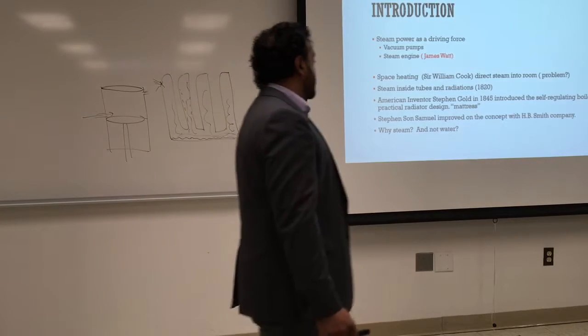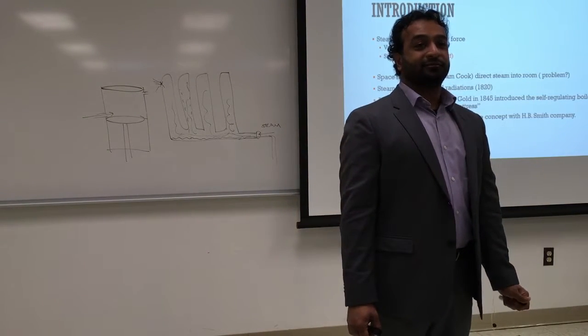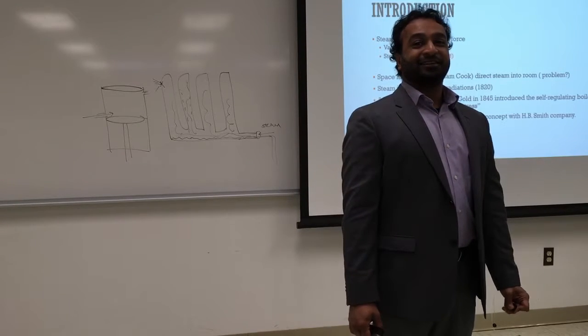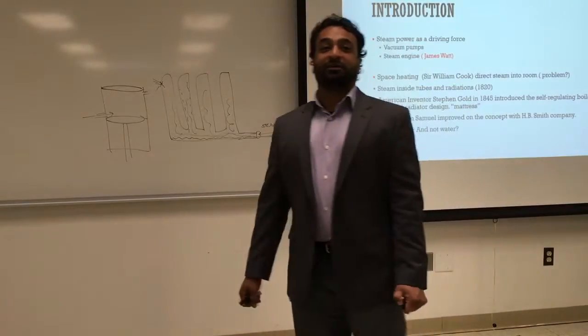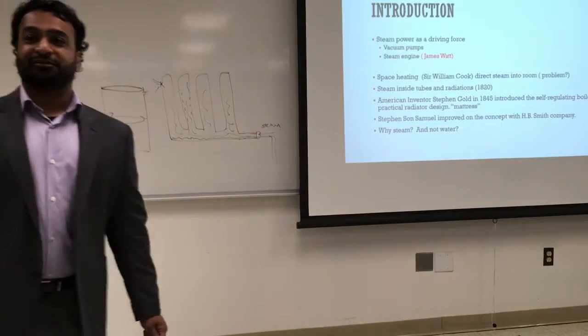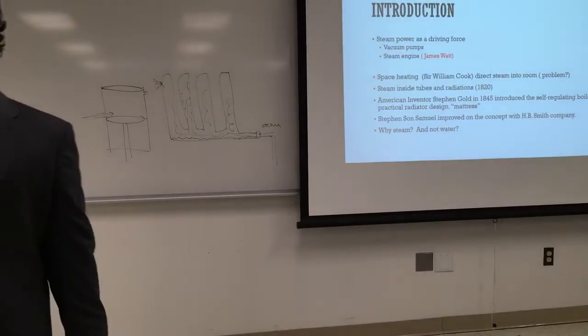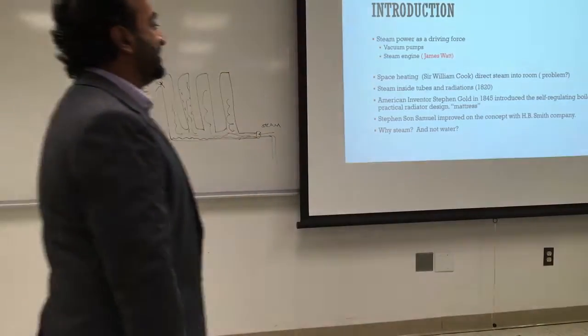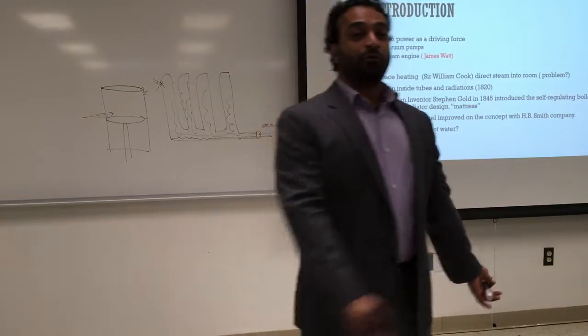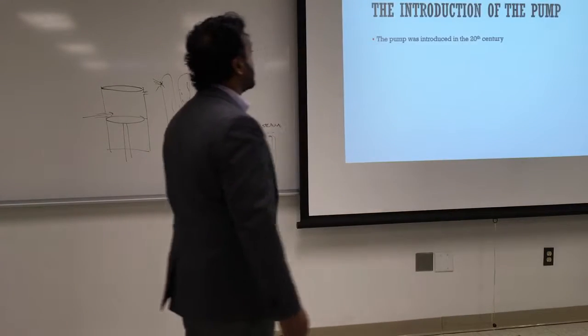Why did heating start with steam and not hot water? Because we did not have pumps back then — the pump was not invented until around 1920. With steam you don't have to pump it, it goes on its own lower pressure. With hot water you have to pump it. Around 1918 water started being used in heating systems and hydronic hot water systems began — it was less expensive because you only need a boiler that goes to 180–200°F instead of a thick, over-designed steam boiler.